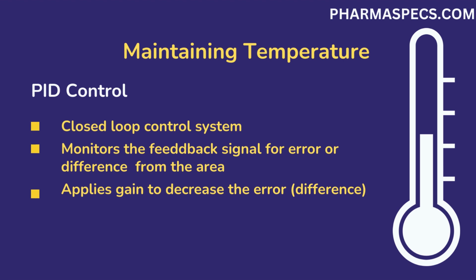Another method called the PID method is a closed loop method. In PID control method, full power is not applied. Instead, there is a feedback signal which calculates the difference between the set point and the actual temperature. As the temperature reaches near the set value, it decreases the output. When set point is achieved, it only outputs a minimum value to maintain the temperature at the required value. The output is controlled through gain, which is the input from main controller to temperature control system.